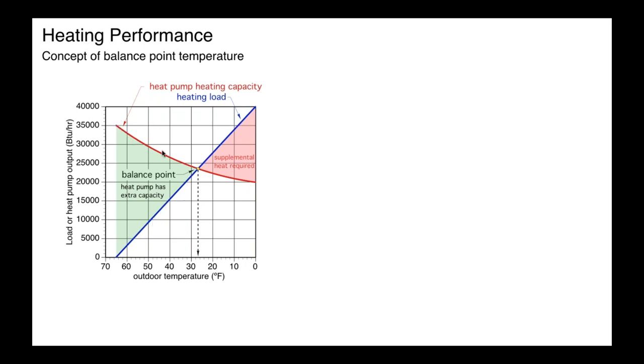Well, here's a heating capacity curve for a heat pump. And as it gets colder outside, as we've talked about, the capacity goes down. So at some point, these curves are going to cross. At some point, the output of that heat pump is exactly equal to what the load is. And that's called the balance point. A perfect world would be where the outside temperature, in this case it looks like about 27 degrees, would be the balancing point. Well, if it just stayed 27 degrees outside, the heat pump could run continuously and exactly match the heating load of the building. Well, obviously that doesn't happen.